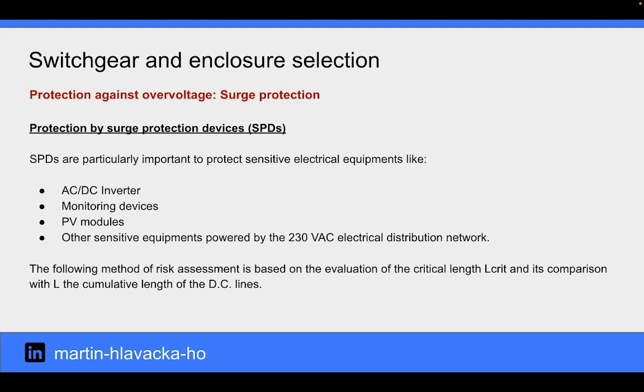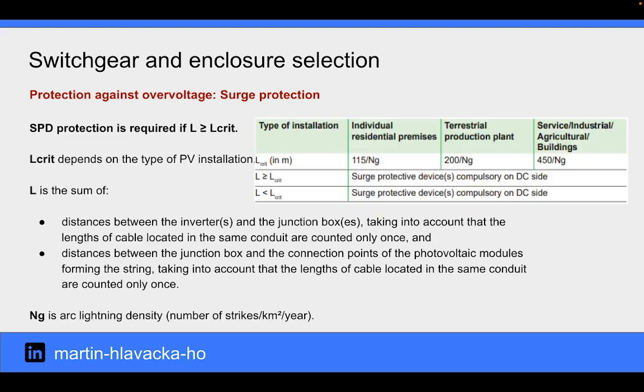The following method of risk assessment is based on the evaluation of the critical length and its comparison with the cumulative length of the DC lines. SPD protection is required if the cumulative length of the DC lines equals to or is greater than critical length. Cumulative length is the sum of distances between the inverter and the junction box, taking into account that the length of cable located in the same conduit are counted only once, and distances between the junction box and the connection points of the photovoltaic modules forming the string, taking into account that the lengths of cable located in the same conduit are counted only once.